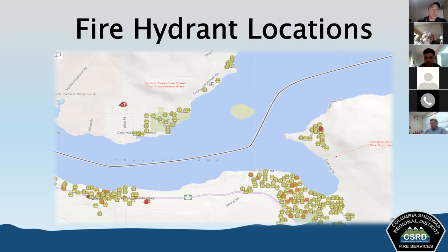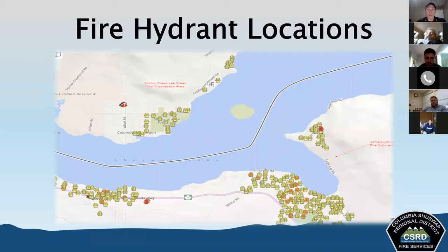This was probably one of the more densely populated shots I could get with hydrants, because not a lot of our areas have access to fire hydrants. Where we put these hydrants is going to be according to local standards and nationally recommended practices. They're typically based on the type of occupancy, construction, building size, population, building density, and the size of the water mains. They're all going to dictate where we put these hydrants. In larger municipal areas, you may find one every 500 feet in residential areas, 300 feet in very high value areas, and possibly at every intersection as well. That's not going to be the case for most of us in rural firefighting.